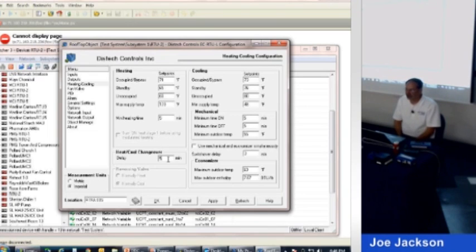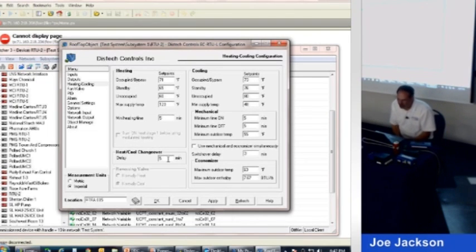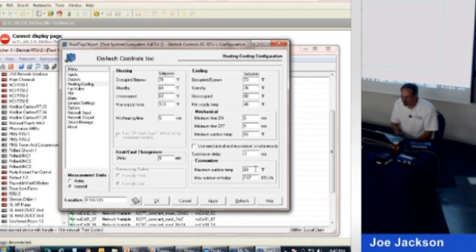Changeover delay. That means if somebody is playing with the thermostat and you're in heating mode and all of a sudden they flip it real cold and take it over to the cooling mode, it's going to wait there for 5 minutes before it swaps. That way, if somebody's banging it back and forth, it's not sitting there heat, cool, and going crazy. The economizer, we're going to let the economizer run any time it's below 60 degrees outside. And if we would have put outside air temperature and humidity on it, it would have calculated enthalpy and said if we are less than 7.67 BTUs per pound of air, we're going to let the economizer run. We didn't add an outside air humidity sensor, so it can't calculate enthalpy, so it'll ignore that.